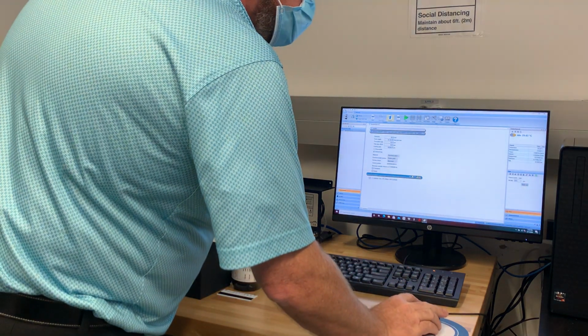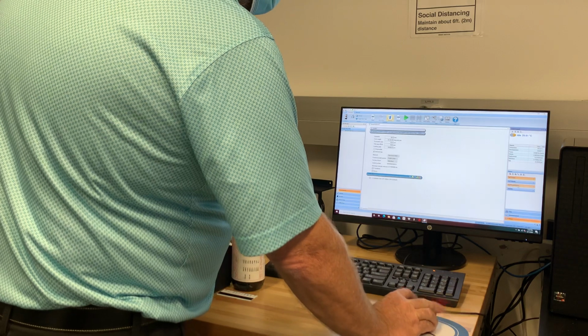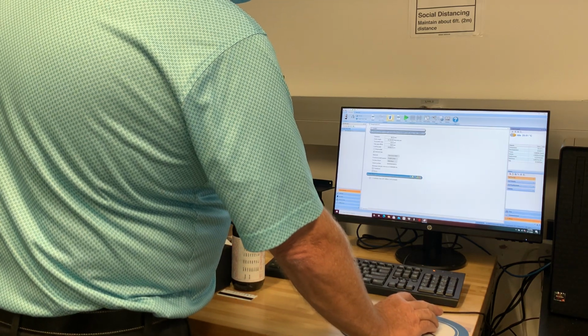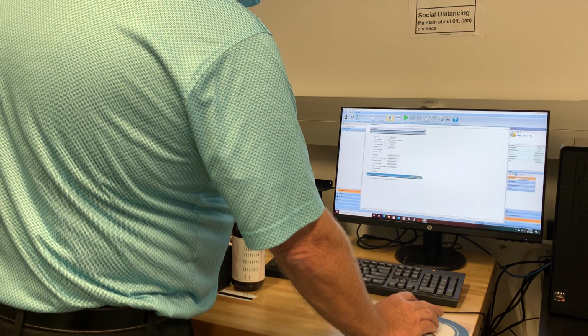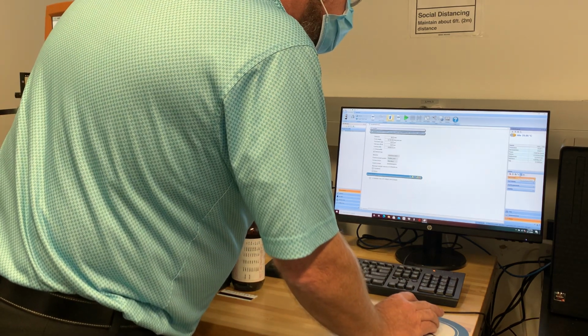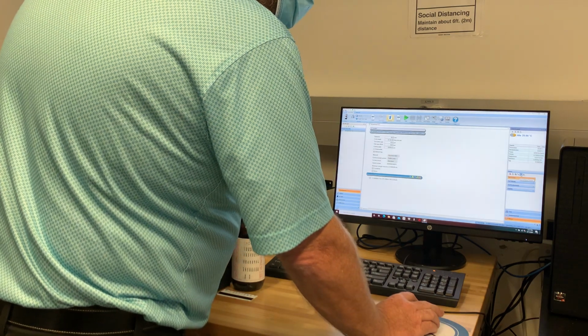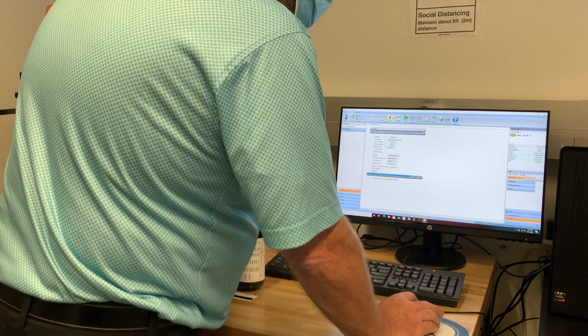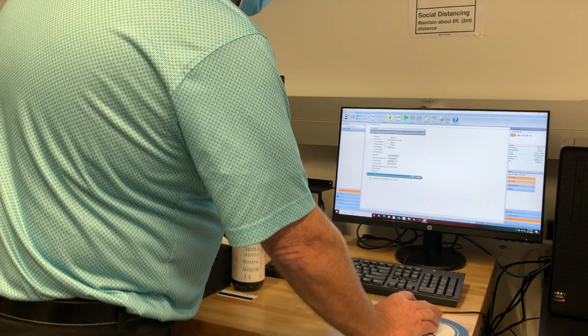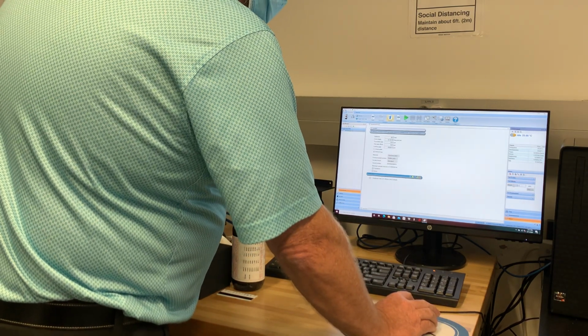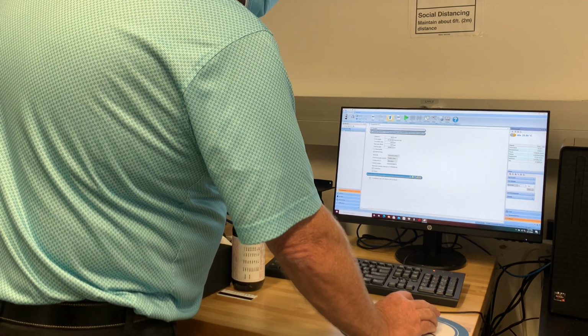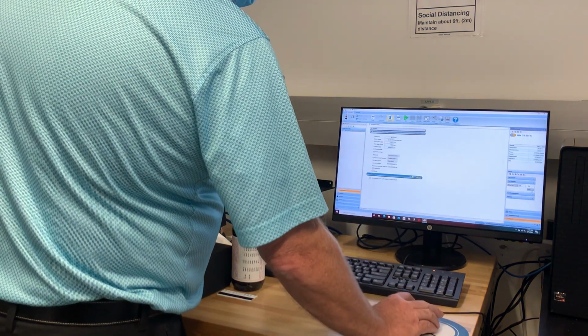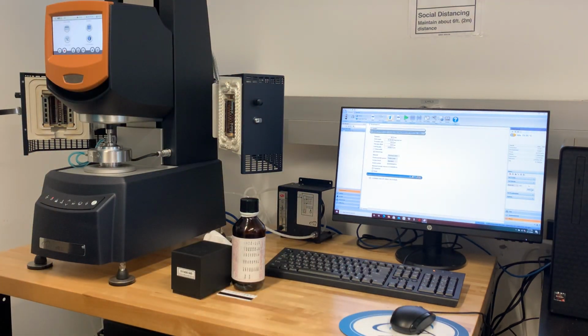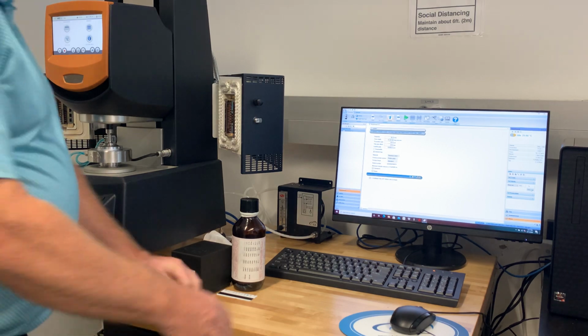So what I like to do when I'm running a test like this with a fluid is go to the motor control, where you can lock it, zero displacement, do a manual oscillation, go to a home position, and move to an alignment position for other types of geometries you don't have. But we can also set a shear rate. I like to get the geometry turning a little bit, especially for a fluid, in case there are any bubbles, to try and work them out.